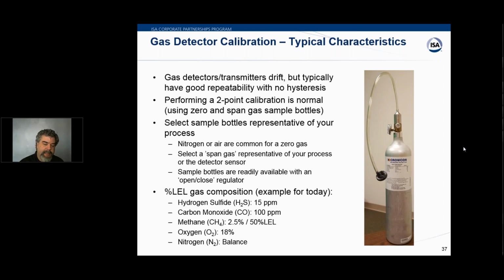Right now we're testing for methane, so just ambient air will be just fine for that. So the bottle that Ned has, you can see it on your screen there. It's got a number of different characteristics, so you could utilize this for a number of different things. It has 15 parts per million hydrogen sulfide, 100 parts per million carbon monoxide, 2.5% or the 50% LEL, lower explosive limit on methane. It's 18% oxygen, and the remainder is nitrogen.